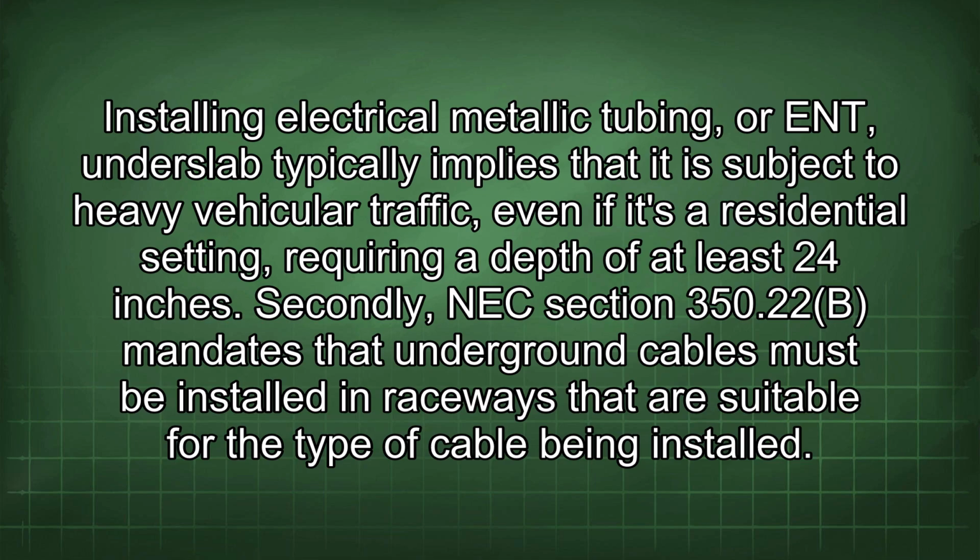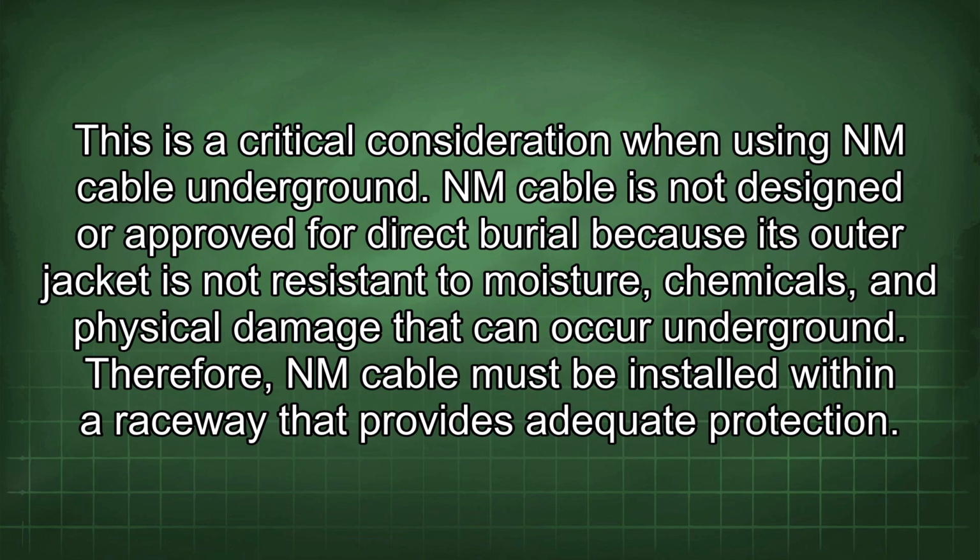Secondly, NEC Section 350.22b mandates that underground cables must be installed in raceways that are suitable for the type of cable being installed. This is a critical consideration when using NM cable underground. NM cable is not designed or approved for direct burial because its outer jacket is not resistant to moisture, chemicals, and physical damage that can occur underground. Therefore, NM cable must be installed within a raceway that provides adequate protection.